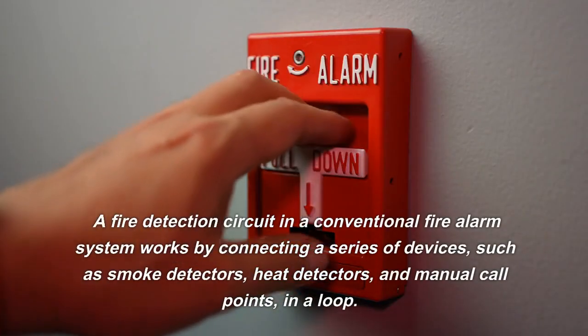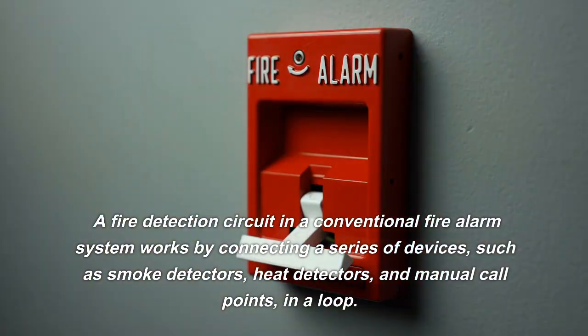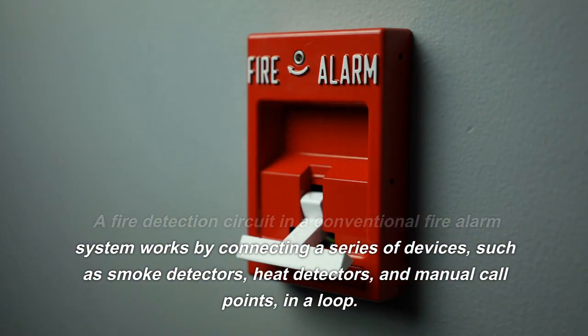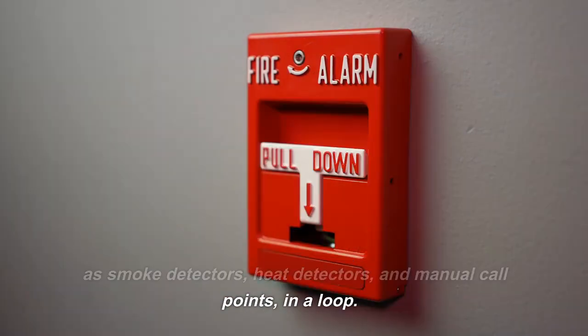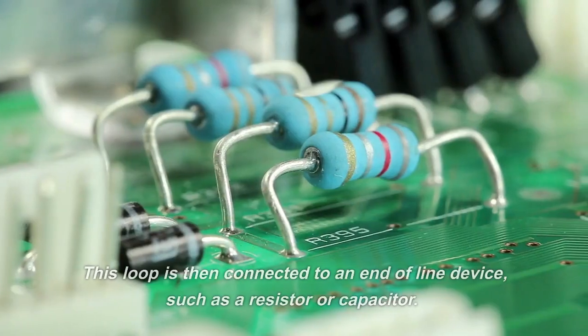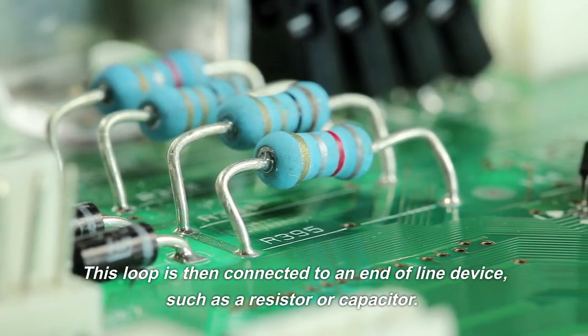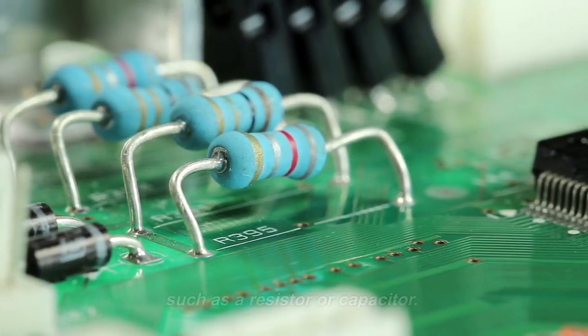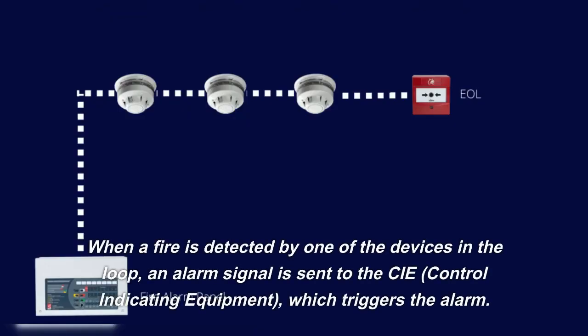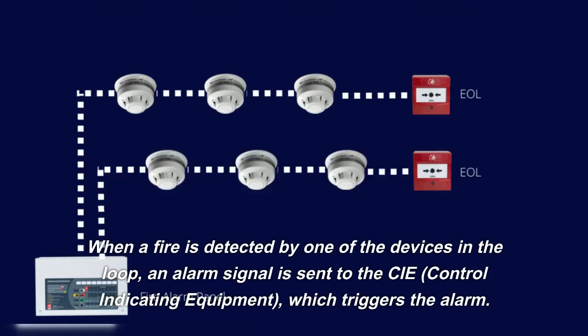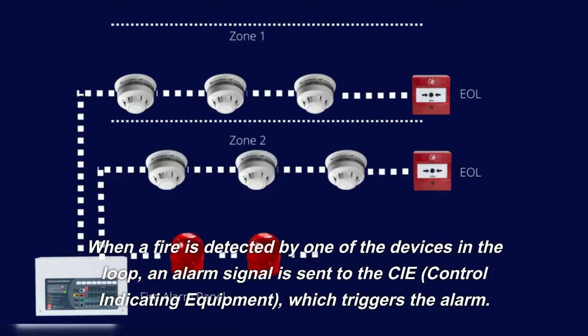A fire detection circuit in a conventional fire alarm system works by connecting a series of devices, such as smoke detectors, heat detectors, and manual call points, in a loop. This loop is then connected to an end-of-line device, such as a resistor or capacitor. When a fire is detected by one of the devices in the loop, an alarm signal is sent to the CIE, control indicating equipment, which triggers the alarm.